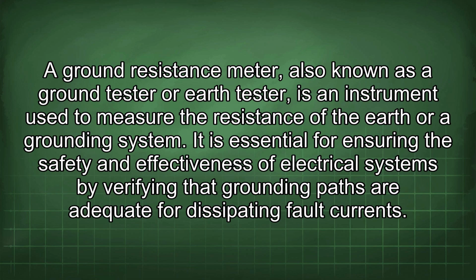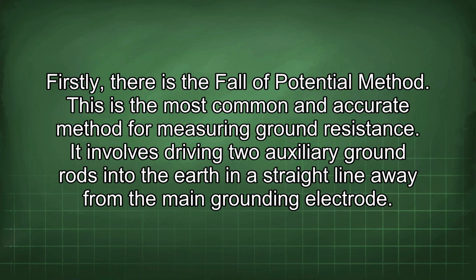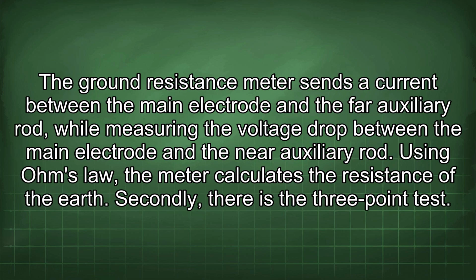Firstly, there is the fall-of-potential method. This is the most common and accurate method for measuring ground resistance. It involves driving two auxiliary ground rods into the earth in a straight line away from the main grounding electrode. The ground resistance meter sends a current between the main electrode and the far auxiliary rod, while measuring the voltage drop between the main electrode and the near auxiliary rod.